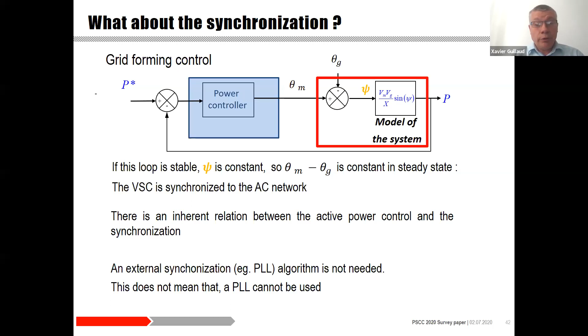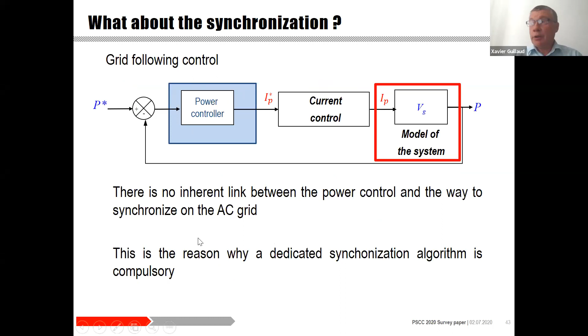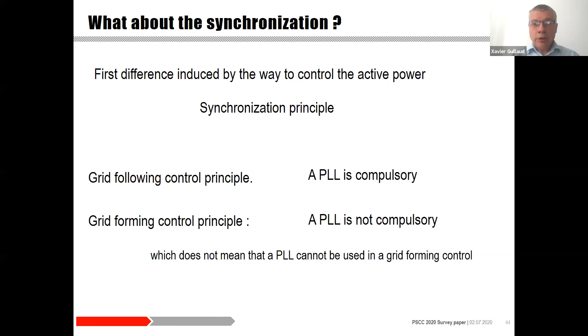Obviously, there is no inherent link between the power control and the way to synchronize to the AC grid in the grid following control. This is the reason why a dedicated synchronization algorithm is compulsory in this case. So, to conclude this point, the first and major difference, which is induced by the way to control the active power, is the synchronization principle. The grid following controller needs a PLL. This is compulsory. For the grid forming controller it is not compulsory, but it doesn't mean that the PLL cannot be used in a grid forming control. Just say that it's not compulsory. Sometimes it can be very helpful. We will see that further.